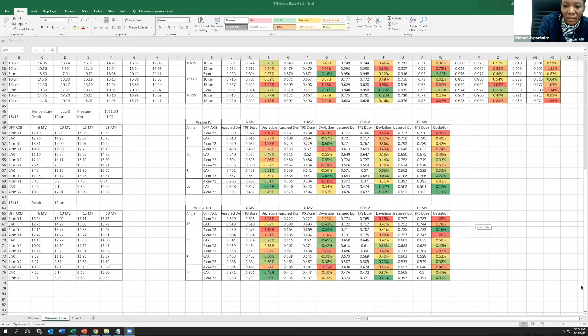Okay, now these are the results of the point dose measurement. We had to do it for different energies and different field sizes, both symmetric and asymmetric. We calculated at different depths to compare the measured dose with the treatment planning dose. Everywhere here the deviation is small, and the majority are not even up to 0.5% deviation for the point dose measurement. Looking at all these deviations, we have been able to verify that our treatment planning commissioning is okay.